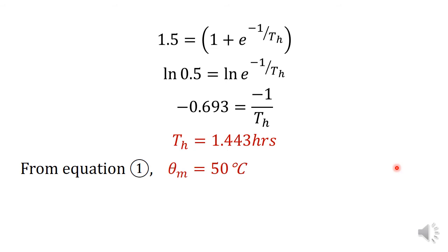Substituting th back into equation 1 or equation 2, we obtain the value of theta_m as 50 degrees Celsius. So the final steady state temperature rise is 50 degrees Celsius and the heating time constant th is 1.443 hours. These are the two values required for the first part of the question.